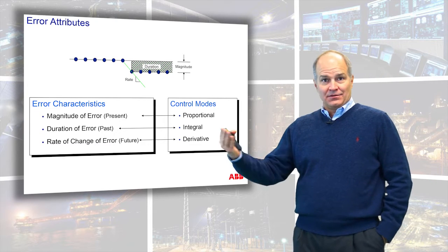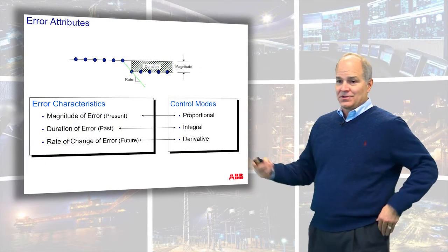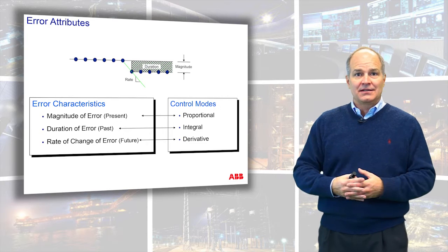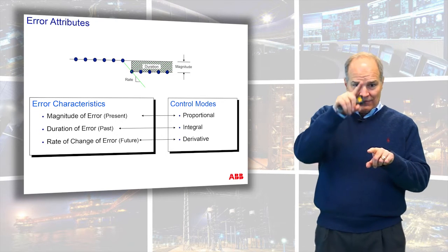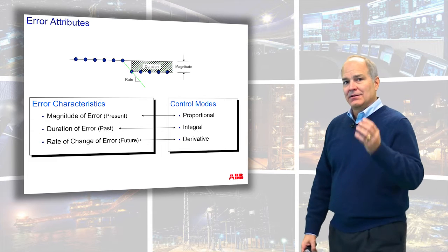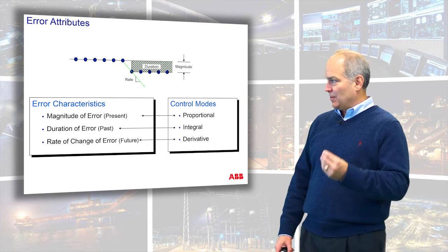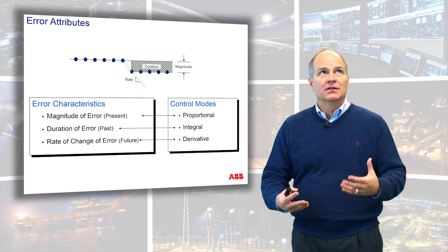If you notice, there's proportional, integral, and derivative — three parameters in a controller. What do those line up with? Proportional control is designed to work with the magnitude of the error. Integral control is designed to deal with the past error or the area under the curve. And the derivative is designed to deal with the future error or the rate of change. So in mathematical terms, proportional is like a teeter-totter. Integral is looking at the area under the curve and translating that into an output. And derivative is looking at how fast this change occurs and trying to adjust the output based upon that.